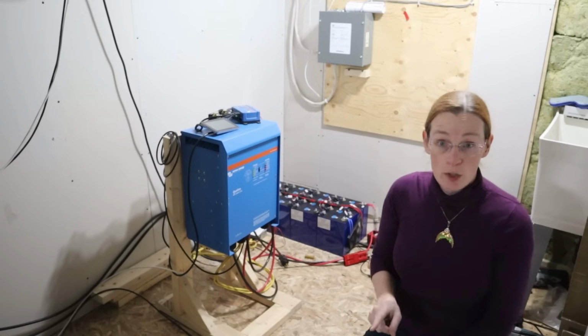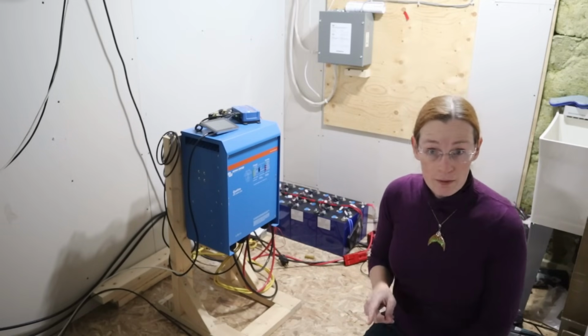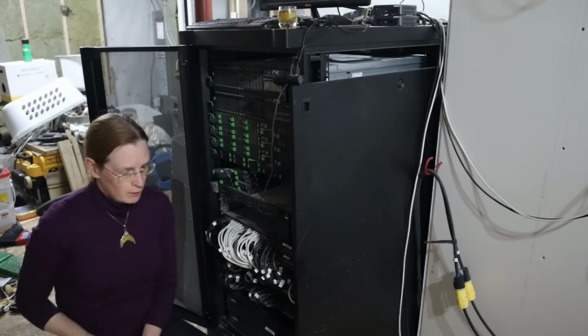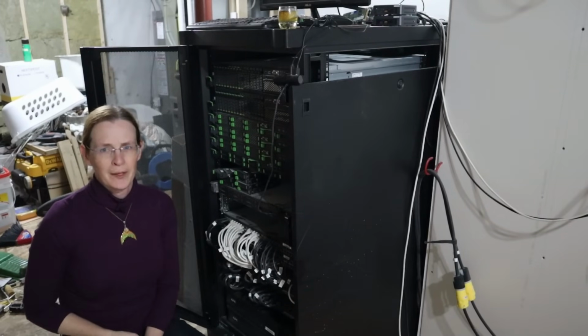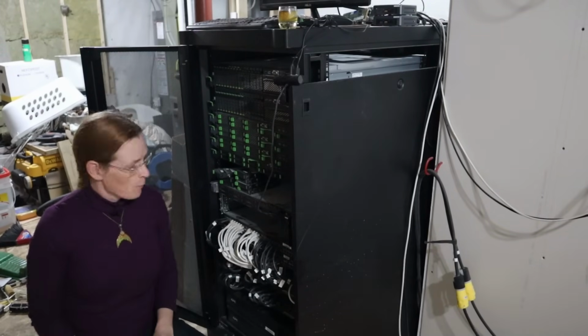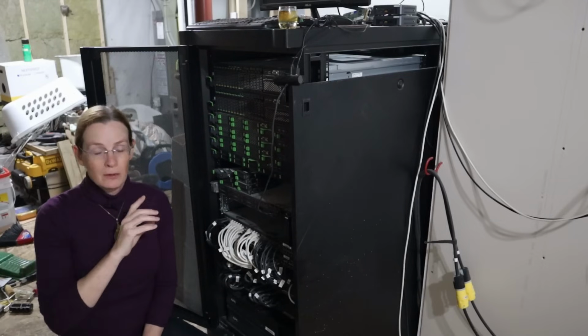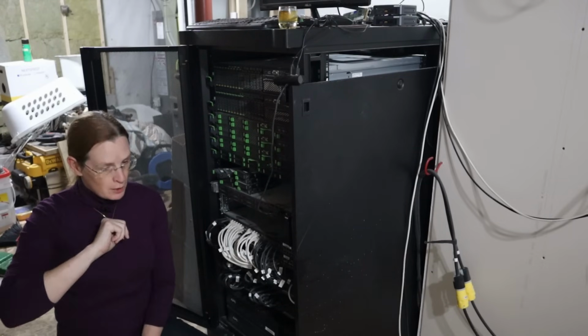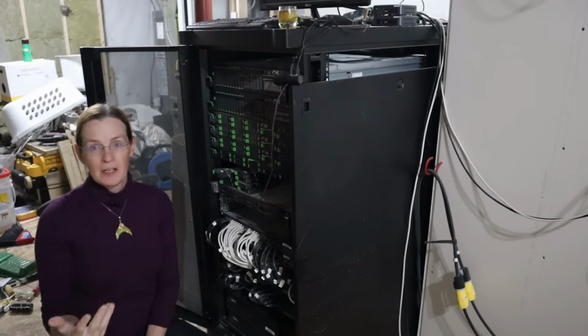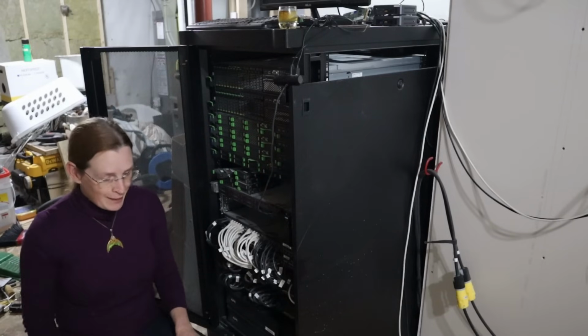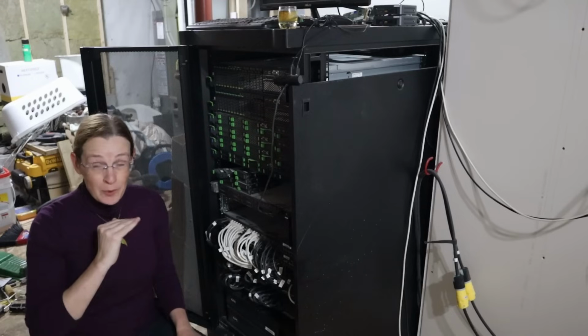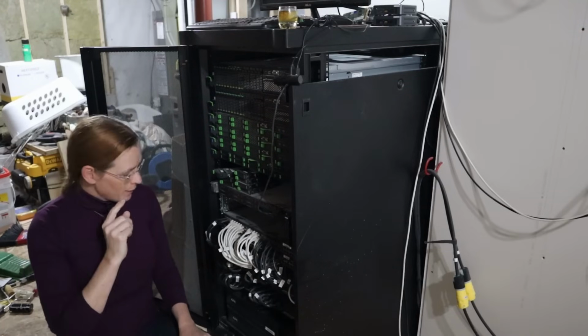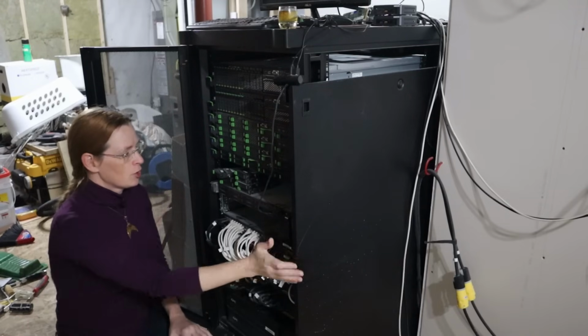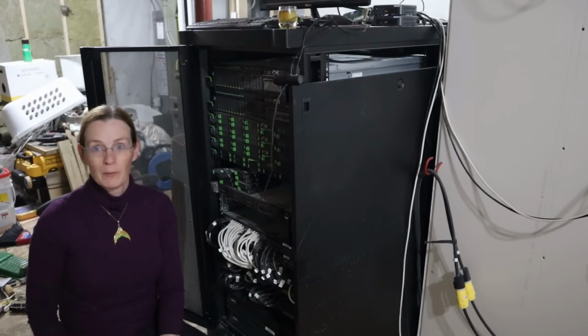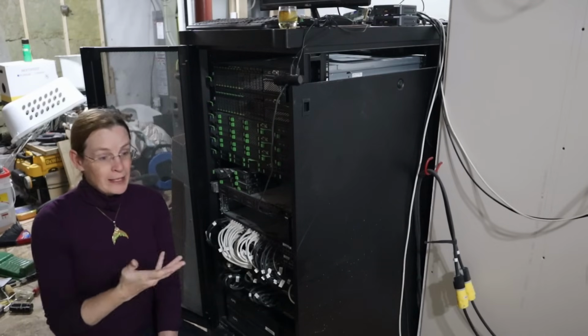So now I need to do the load test. To do that, we're back at the rack of servers, which is a fair bit dustier now, but so it goes. My plan currently is to turn the Quattro back on, start charging it again because it's been self-discharging a bit after I moved everything back down. So I know that it's top charged. Then I am going to turn on the inverter, turn on the rack of servers - that was probably loud - and run it until the batteries die.